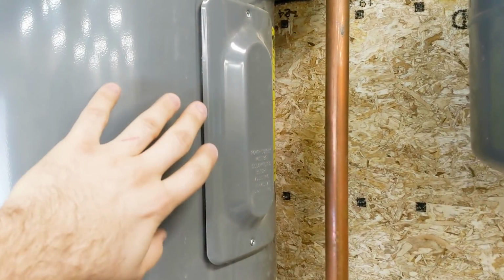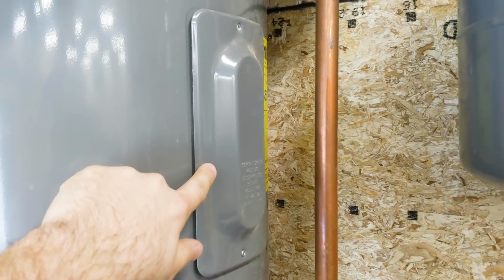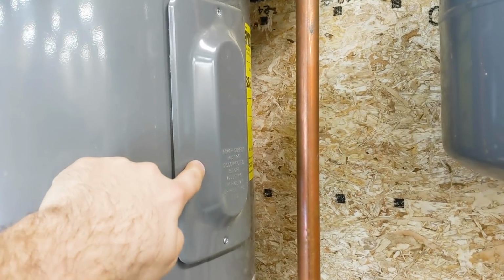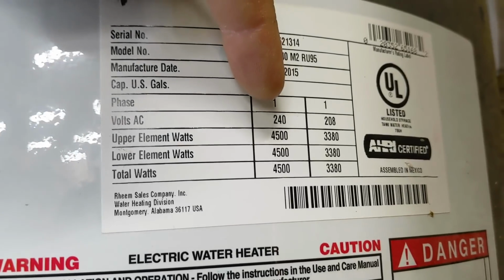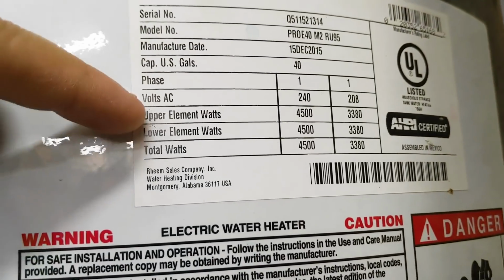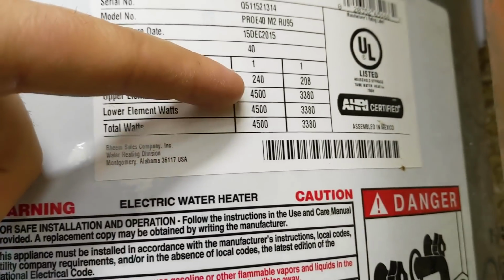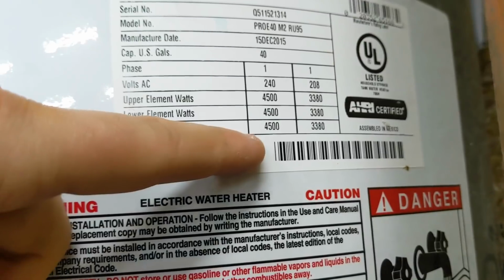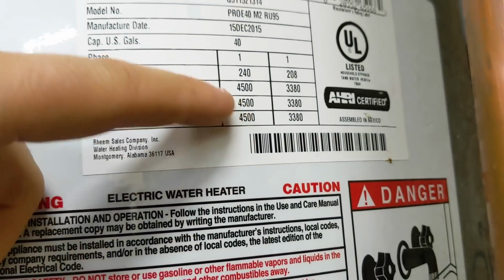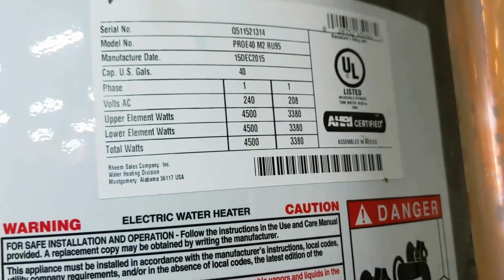The first thing we have to do is turn off the circuit breaker to this. Then we're going to take this cover off and disconnect the wires that go down. We're running 240 volts, and both the upper and lower elements are 4,500 watts each, but notice the total is still 4,500 watts since only one is on at a time.